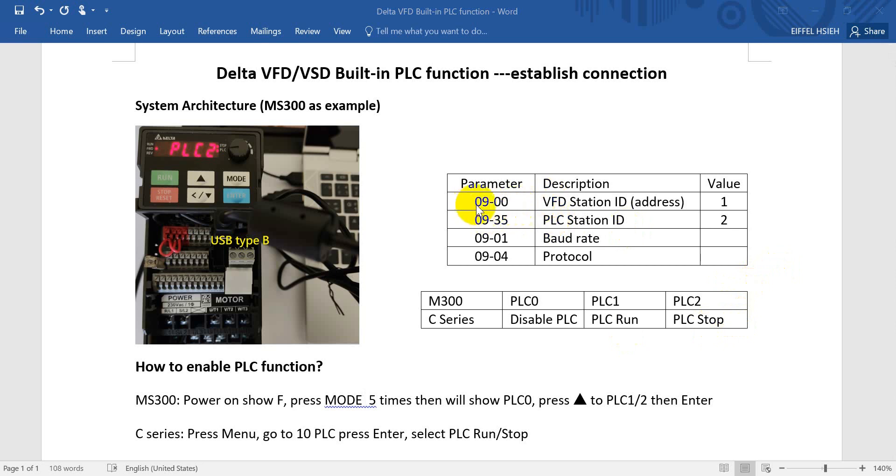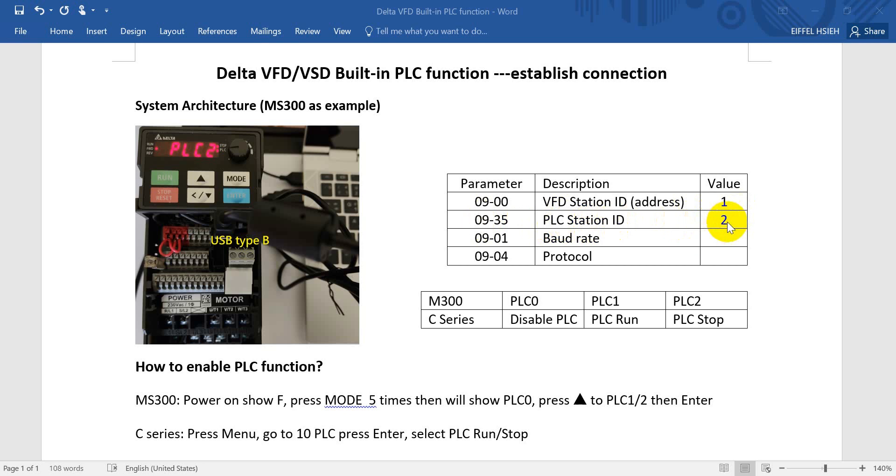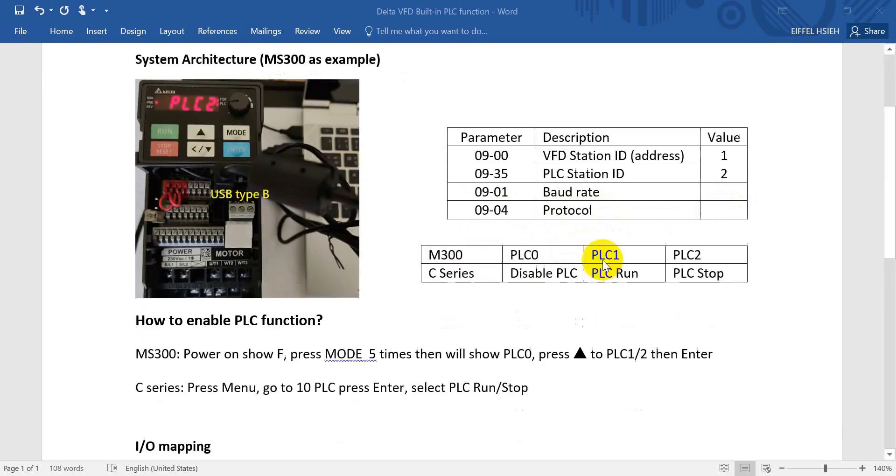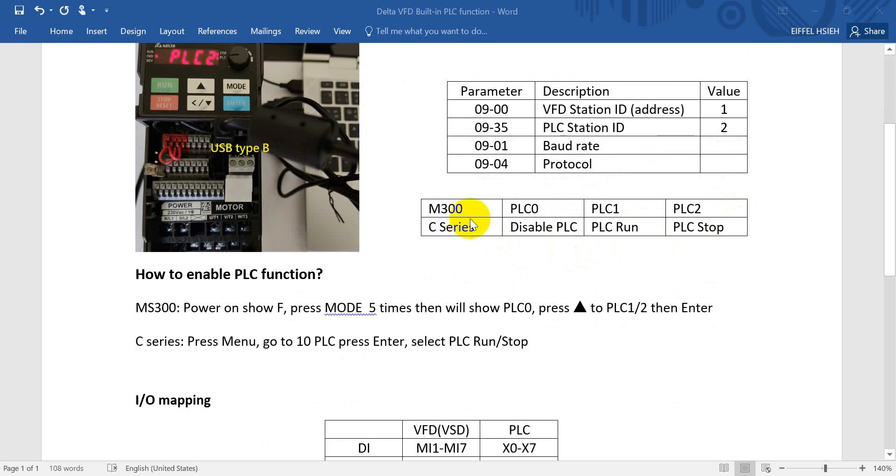And here we will talk about some important parameters for the inverter. So most of you should know that 09-00 is for inverter station ID or station address. This default value is 1. And for PLC we will use another ID address, so this one default value is 2. Regarding baud rate and protocol, that's up to your application.